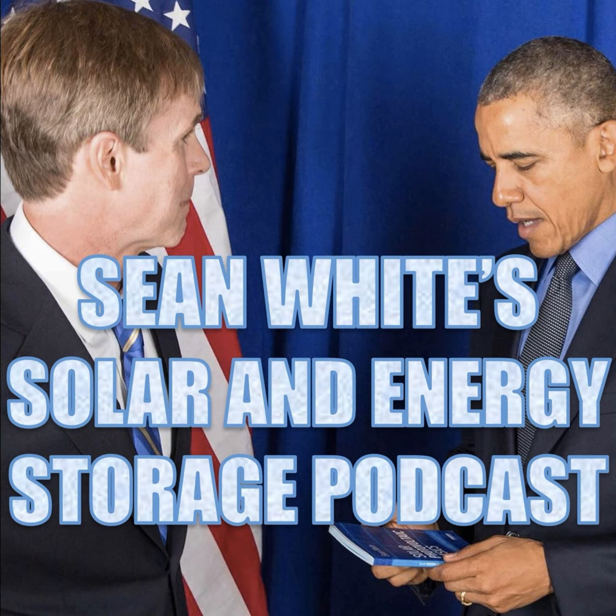And so if you touch two wires, then you can make a circuit again, like from the positive and the negative. You've touched positive to negative and it can make a circuit there. So there's voltage there. And actually, the voltage goes up by 25% when you turn it off on the PV side. And that's because if you look at what's called an IV curve, you go from operating voltage to open circuit voltage, which is off, which is about 25% more voltage than when it's on.